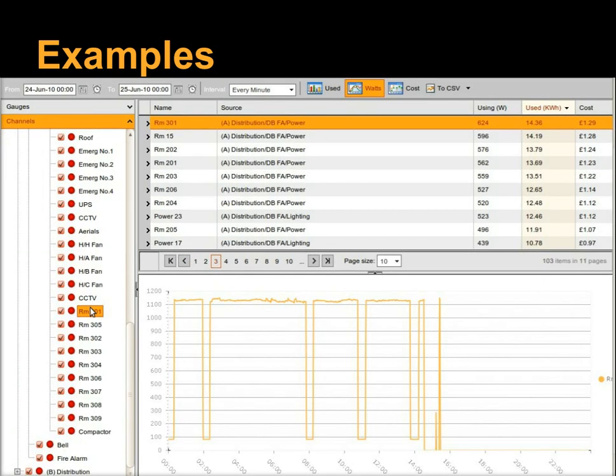Let's move to another education establishment. This is a sixth form college, a 70s-odd building. Not particularly interesting, but we were able to go to each one of the rooms for the lighting, the power and so forth. And we showed, in the environmental unit, the power being used in their own classroom. And they were very confused by this particular power signature. They wanted to know what used more during the night than it did during the day. So they went around and they switched things off. And eventually they found that one of these through-the-window AC units was actually on all the time.